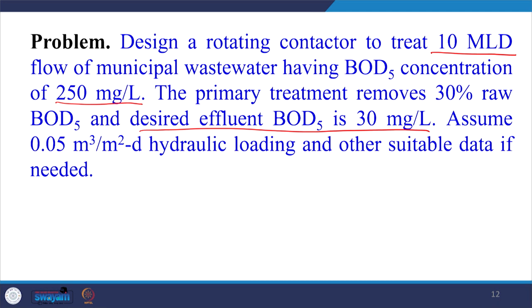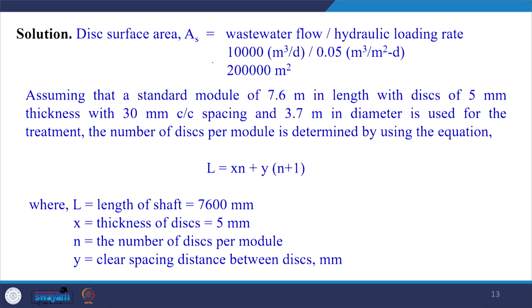We assume a hydraulic loading of 0.05 m³/m²/day. The disc area required can be calculated as follows: waste water flow rate is 10 MLD, which is 10,000 m³/day. Dividing by the hydraulic loading of 0.05 m³/m²/day, we get a required disc area of 2,00,000 m².